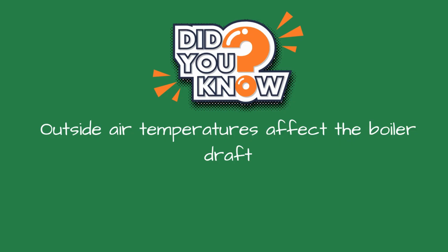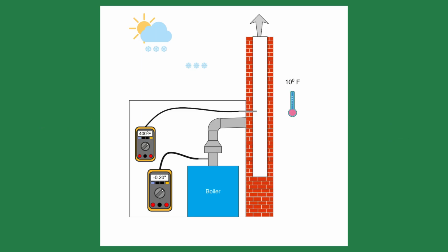Did you know outside air temperatures directly influence draft? Let me explain how. When it's cold outside, the temperature difference between the flue gases and outdoor air increases. That means a higher draft. Sounds great, right? Well, not always. Higher draft can pull the flue gases out too fast, like we discussed.